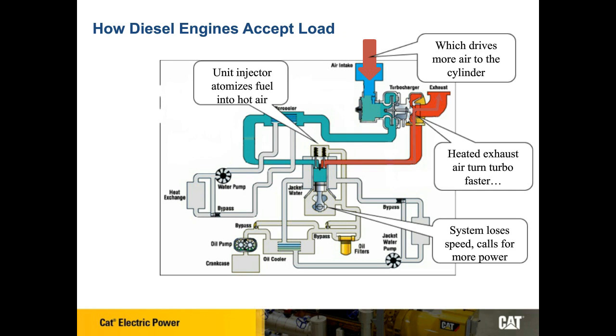If you look in the middle of the diagram, you can see the piston, the engine, and a box that says, when the load is applied, the engine loses speed. That's how the engine knows it needs more power. So it responds by injecting more fuel directly into the cylinder, which produces more heat in the exhaust, which drives the turbocharger faster and pushes more air into the cylinder to burn more fuel on the next revolution. So this is a really quick feedback loop. The engine's able to respond very, very quickly just by immediately injecting more fuel into the cylinder.